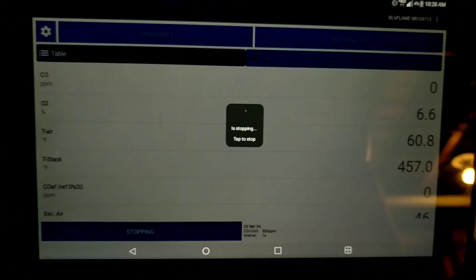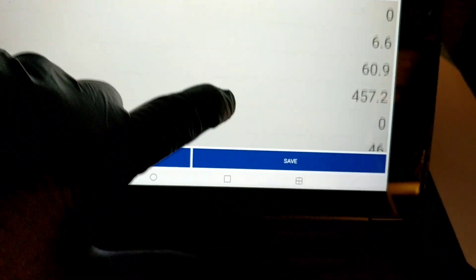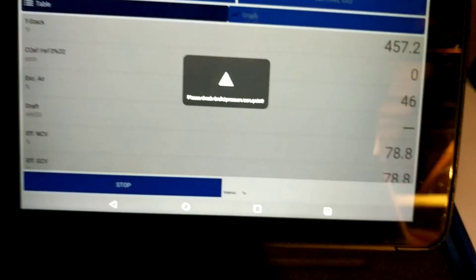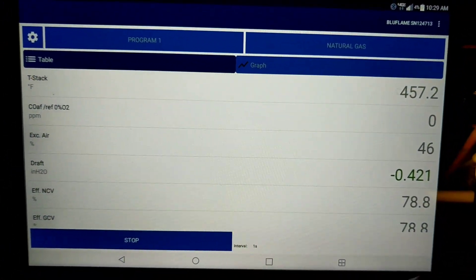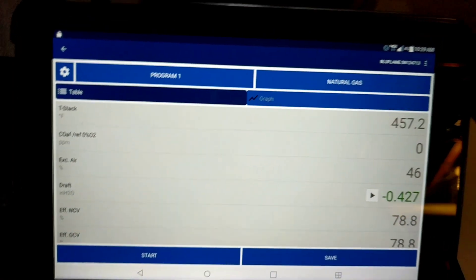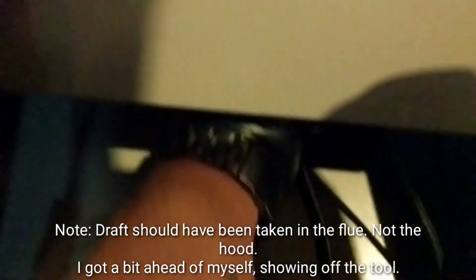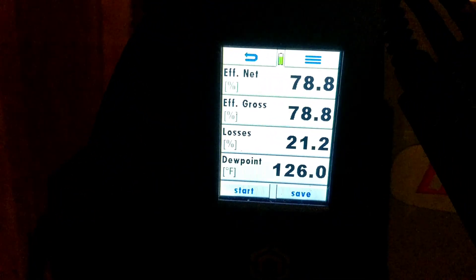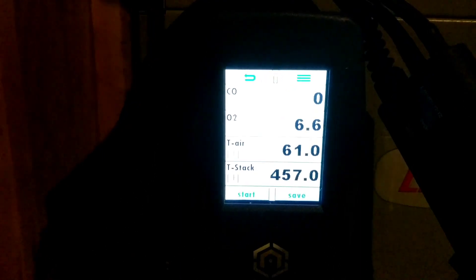So we can stop our machine here when we want to take a draft reading. Our pump stops over there, we start taking our draft, and it starts populating here. We can hit stop and it stores that number in there. You can hear the pump start up again — what the pump is doing is it's post-purging any of the combustion gases out of the machine after it stops. You can see our numbers aren't changing because it's not taking any more readings; it's just doing a kind of post-purge getting all the stuff out.